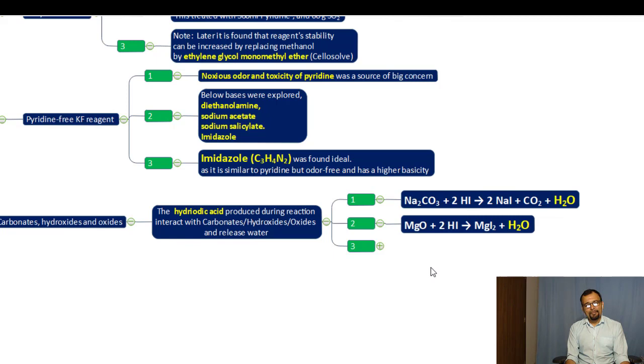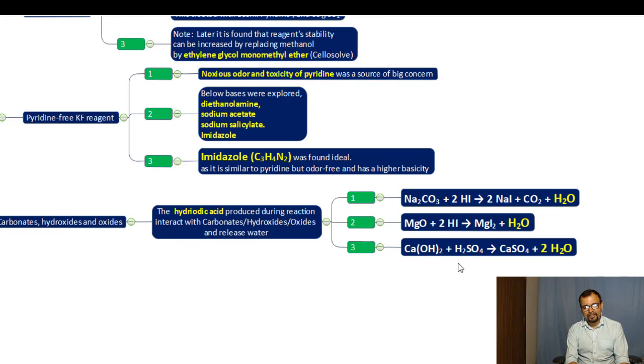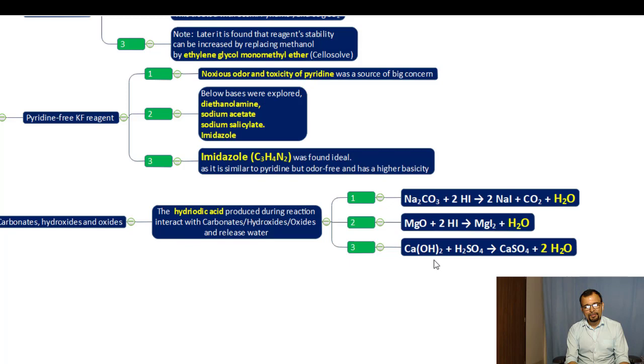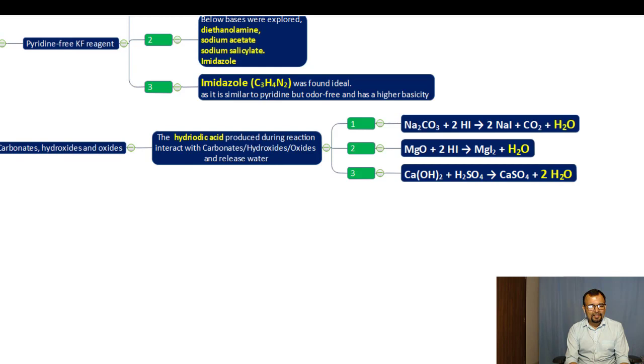Magnesium oxide reacts with hydroiodic acid and releases water molecules. Calcium hydroxide interacts with the sulfuric acid generated during the KF reaction, and calcium hydroxide can also release water molecules. These interactions make the KF reagent unsuitable for samples containing carbonates, hydroxides, and oxides.